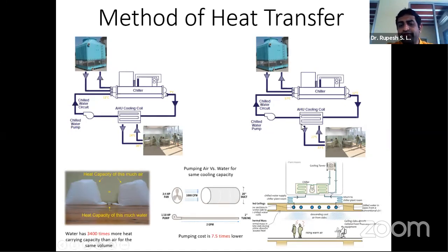Now with the radiant cooling kind of system, the delta T between these will only increase. So my chiller outlet could be as high as 12 degrees and my chiller inlet could be as high as 17 degrees, because for the water running in these pipes, I don't have to have that coil temperature of about 13 or 14 degrees. I can have the water running temperature at about 18 to 19 degrees Celsius. So this 5 degrees delta T on the low side could affect my high side itself. And the chiller which is running at a higher inlet and outlet temperature will obviously have a better efficiency.